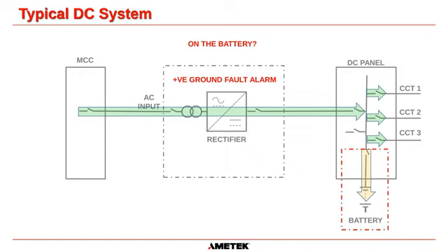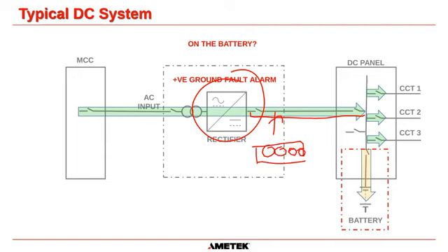So then the next easy thing to do without dropping the load circuits, hopefully, is with leaving the charger online. Now, you do have to make absolutely sure that your charger rectifier can maintain your load circuits without a battery. I don't know why some people call it a battery eliminator charger. I hate that term because it doesn't eliminate a battery. It just allows the charger to maintain its 135 volts load because it's got a lot of DC capacitors inside it, which filters out the AC content of the output of the charger.